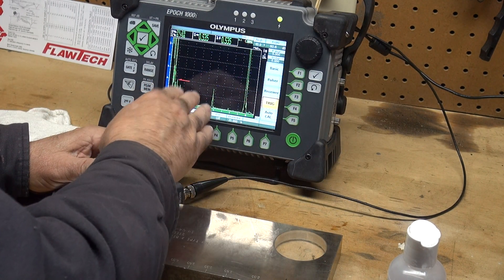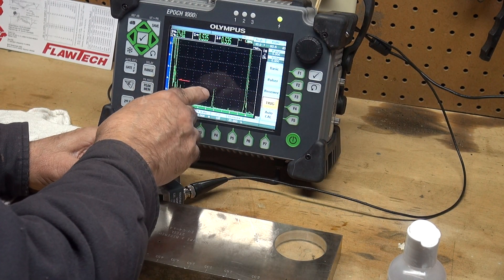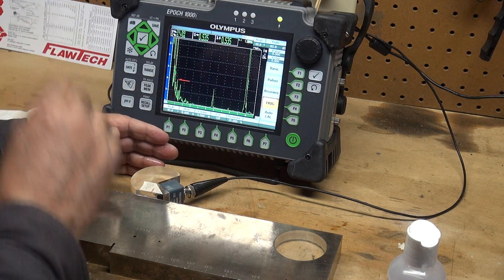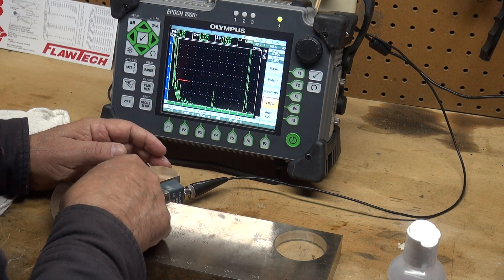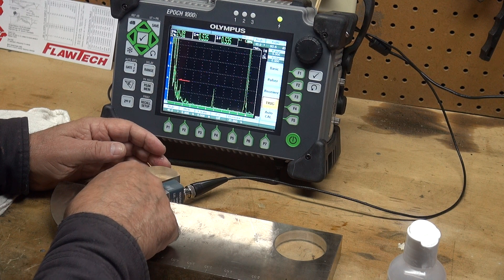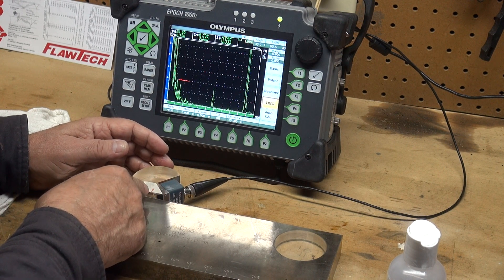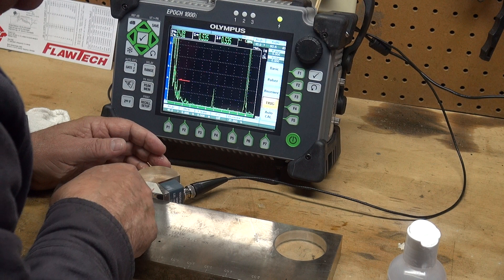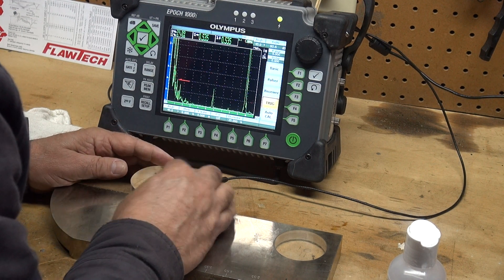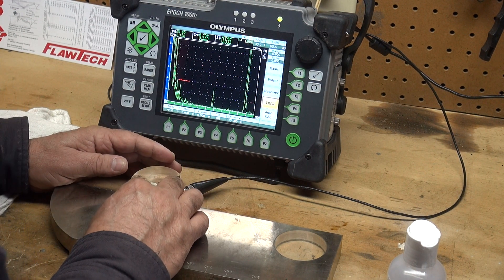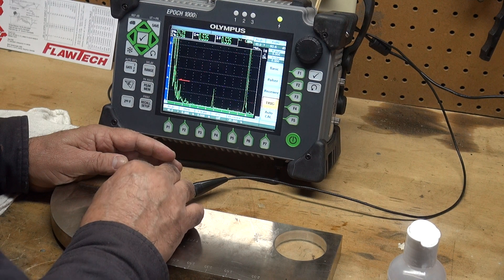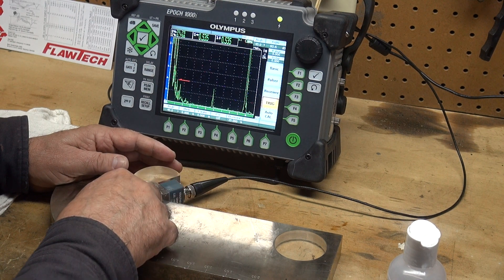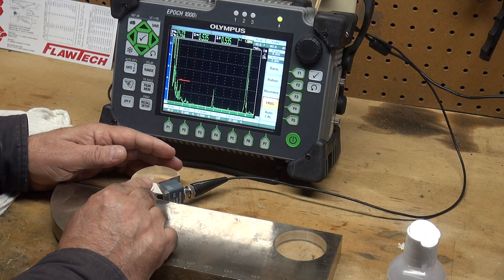I found the peak where that signal is the strongest. I have a piece of tape here and I marked that's my beam index point. I'm marking on this masking tape where that point is aligned with the zero machine mark on the IIW block.